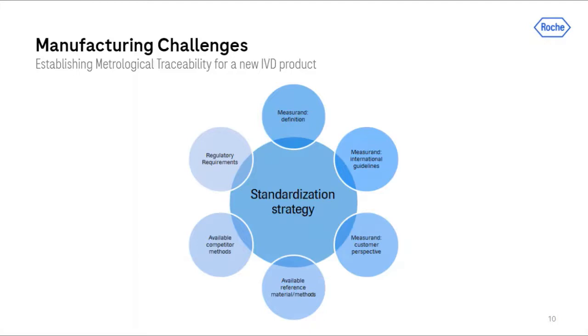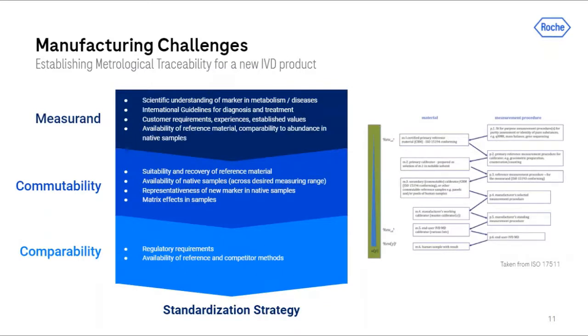For setting up the standardization strategy, several aspects have to be considered: Is the measurand clearly defined? Are there clinical or diagnostic guidelines? Are there customer requirements? Is a reference material or method available? Are there already established competitor products? What is the calibration hierarchy? What are the regulatory requirements in various countries for registering the IVD product? One could differentiate between three perspectives: topics regarding measurand, commutability, and comparability.